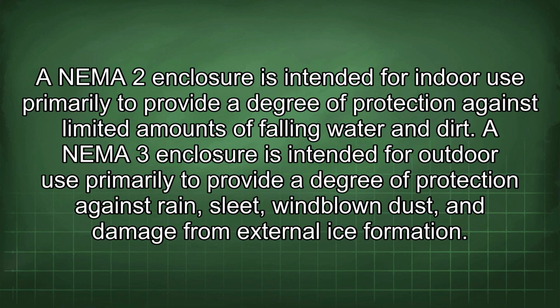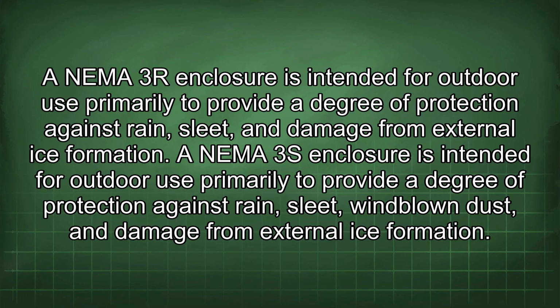A NEMA 2 enclosure is intended for indoor use primarily to provide a degree of protection against limited amounts of falling water and dirt. A NEMA 3 enclosure is intended for outdoor use primarily to provide a degree of protection against rain, sleet, wind-blown dust, and damage from external ice formation. A NEMA 3R enclosure is intended for outdoor use primarily to provide a degree of protection against rain, sleet, and damage from external ice formation. A NEMA 3S enclosure is intended for outdoor use primarily to provide a degree of protection against rain, sleet, wind-blown dust, and damage from external ice formation.